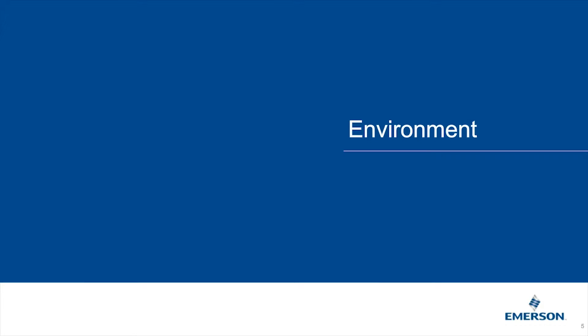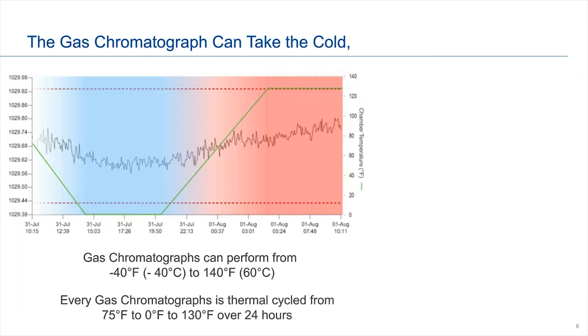So the first topic is the environment. Our GCs and pretty much most manufacturer GCs can take some very cold and very hot environments. Our GCs are actually rated down to minus 40°F or minus 40°C. For hazardous locations, the GC is actually rated from minus 4°F to 140°F, or minus 20°C to 60°C. Every GC out of Emerson is tested or chamber-tested with a thermal cycle: the GC soaks for six hours at 0°F, then ramps for eight hours to 130°F for another six hours — a total of 24 hours of temperature cycling.